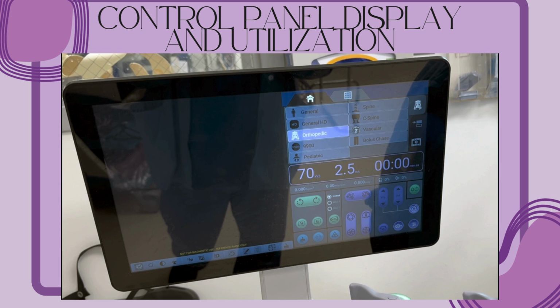So moving on to the left of that, there is a norm, a MAG1, and a MAG2 option. The MAG1 and the MAG2 magnify the imaging and the anatomy for the surgeon if needed. We do tend to stay away from that because it does increase patient dose, because it increases the technique that is needed. To the bottom of that, there is a triangle and a blue circle, and this will turn on and off your laser light, which helps you in centering and positioning the tube while the patient's on the table.